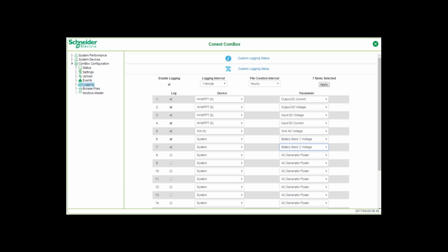For example, AGS, you might want to know why it started. Maybe you have the AGS set up to start on load and trigger on state of charge percentage, and the customer says, hey, the generator keeps starting, and you can go in and see if the trigger was low voltage or low state of charge percentage, or if it started on a load. So virtually any parameter for any device that you can do the custom data logging and at whatever granularity you want to get the data necessary to make an informed decision about what's going on with the particular system.